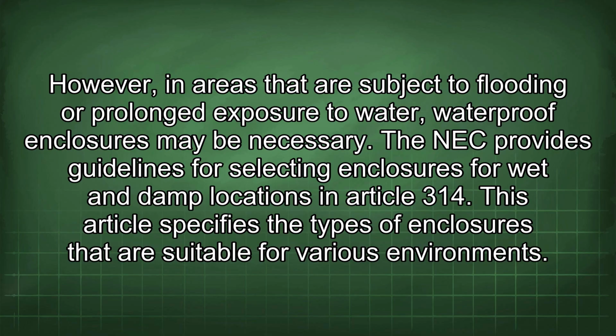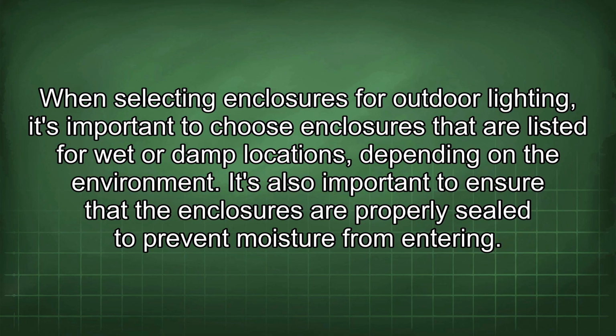However, in areas that are subject to flooding or prolonged exposure to water, waterproof enclosures may be necessary. The NEC provides guidelines for selecting enclosures for wet and damp locations in Article 314. This article specifies the types of enclosures that are suitable for various environments. When selecting enclosures for outdoor lighting, it's important to choose enclosures that are listed for wet or damp locations depending on the environment. It's also important to ensure that the enclosures are properly sealed to prevent moisture from entering.